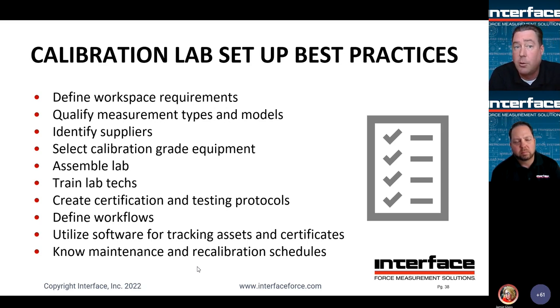You have a torque wrench you need to be brought back into calibration. Who do you go to for that? Is it a defined list of qualified suppliers? How do suppliers get added to said qualified list, et cetera, et cetera. Touched on this on the last slide just a little bit, selecting calibration grade equipment. Making sure that the things you're using for these calibrations are of a sufficient grade of quality to provide the lowest uncertainty possible for a given calibration.